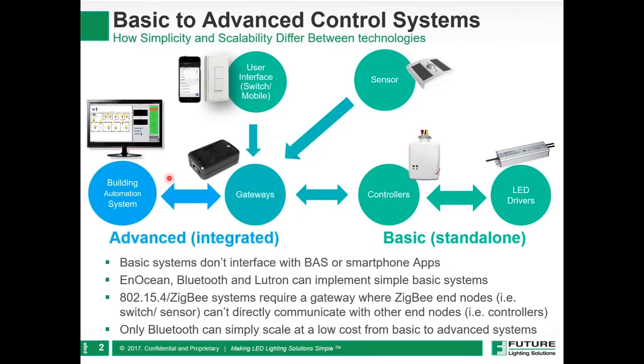However, if there is a building automation system like BACnet, then you do need a gateway here, because there are virtually no LED drivers—frankly, I'm not aware of any—that natively speak BACnet. So the gateway here, at least from a Bluetooth mesh standpoint, is just a simple protocol translator that's going to translate from BACnet to the Bluetooth mesh wireless protocol.